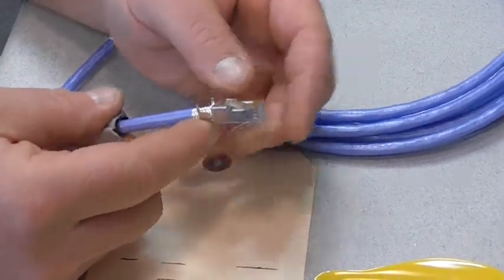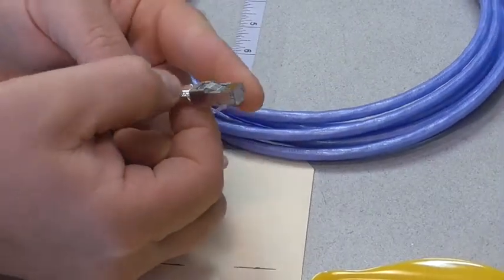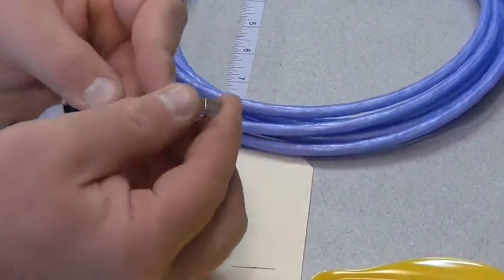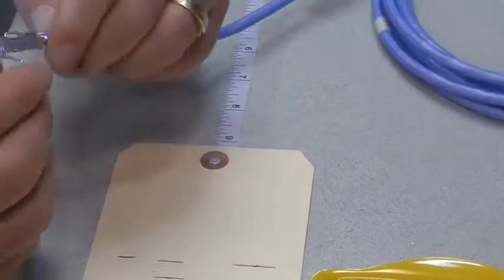Seat all wires fully into the connector until the stranded conductors of each wire are visible through the front end of the connector body. Use magnification as needed.